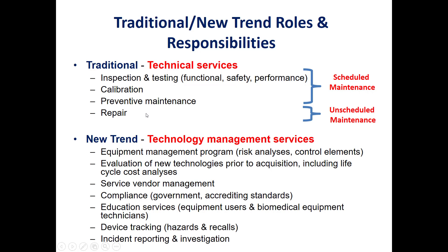In the new trend, we usually cover not only the technical services but also technology management services. This includes the equipment management program, risk analysis and control elements, evaluation of new technologies prior to acquisition through life cycle cost analysis, service vendor management, compliance with government and accrediting standards, training for equipment users and biomedical equipment technicians, and finally device tracking, hazard and recalls, and incident reporting and investigations.